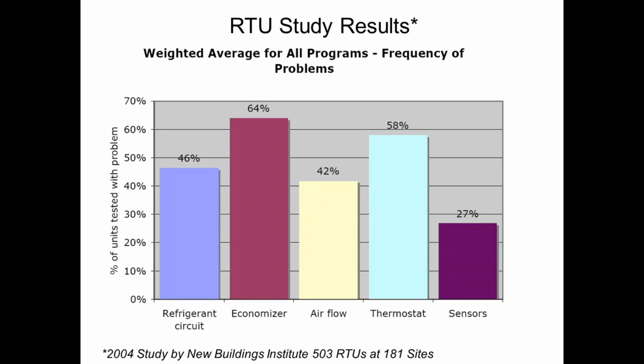And we're going to focus on the economizer thing for now. But 64% of the economizers on those 500 rooftop units were not functioning correctly. They were either screwed shut, propped open, actuator fell off, actuator going the wrong direction, something like that, where basically they weren't opening and closing when they were supposed to do that. Interestingly, Honeywell did their own study, and Honeywell makes a lot of economizer controllers, and their number, 64%.